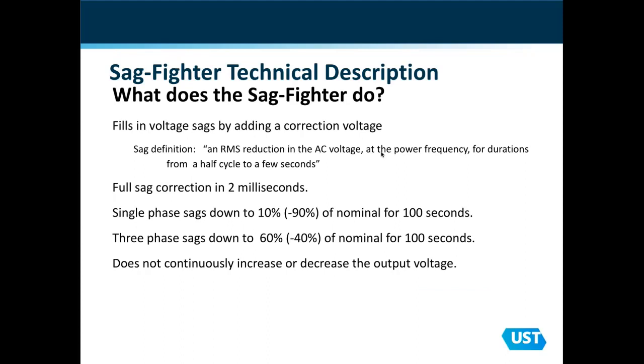So what does a Sag Fighter do? It fills in sags by adding a correction voltage. We make a correction, we recognize a voltage sag. What the device does is it sets a threshold at about 90% of nominal. So anytime the voltage is above 90%, we're simply passing the voltage on through to the load. We're sitting there in standby. When an event occurs, and we set that threshold at 90%, so if the voltage drops below 90%, our control recognizes that and will inject the appropriate voltage on the appropriate phase, and it'll maintain that correction, and the correction accuracy is within plus or minus 5% of nominal.